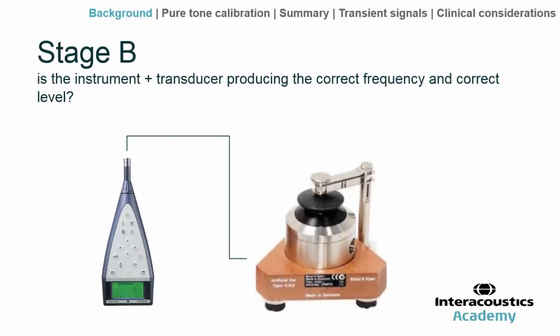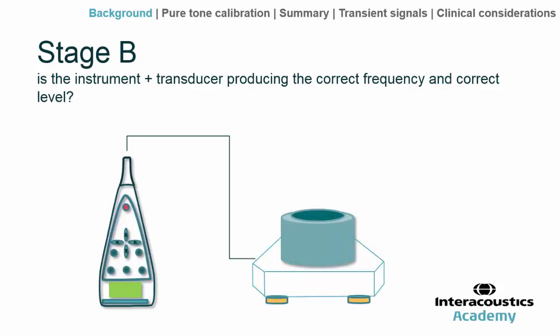For Stage B, with this particular instrument and transducer pairing, the question is: is it producing the correct stimulus frequency and the correct stimulus level? To help answer these questions, we use specialist instrumentation — a sound level meter and a coupler, a device that connects the transducer to the sound level meter to measure its output — essentially a cavity with a microphone to transduce the acoustical input back into an electrical signal.